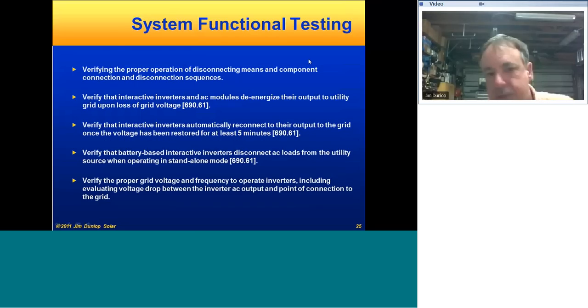Some things on functional testing. Obviously, we're talking about energizing the system at this point and going through some operational checks. These are some very simple things that are based on 690.61 requirements. These are all tests that can be verified to demonstrate the functionality and performance of the anti-islanding provisions in the inverters.